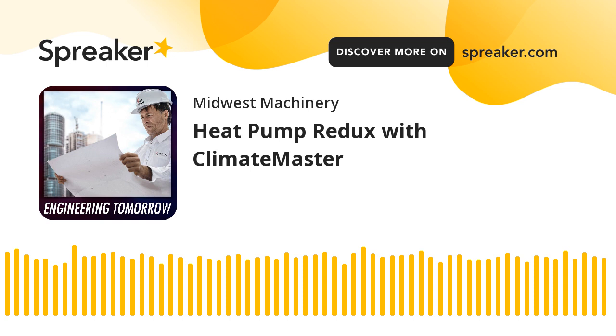ClimateMaster offers three different choices: a single-stage compressor, a two-stage compressor, and we are also rolling out a variable speed compressor for commercial applications. With our variable speed compressor, we can dial down the capacity to about 30%. Along with that variable speed compressor, we have things like an ECM fan motor and a modulating valve and pump in the unit as well. The fourth component of a water source heat pump is the expansion device. Most commonly used is a thermal expansion valve, also known as a TXV. This device meters the quantity of refrigerant flowing through the cycle to meet any load requirements.